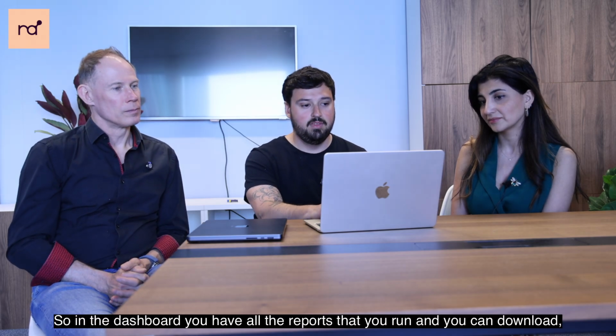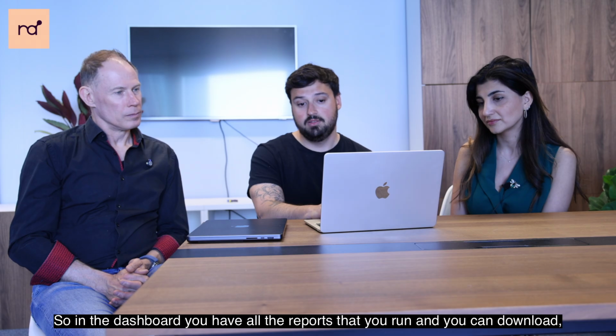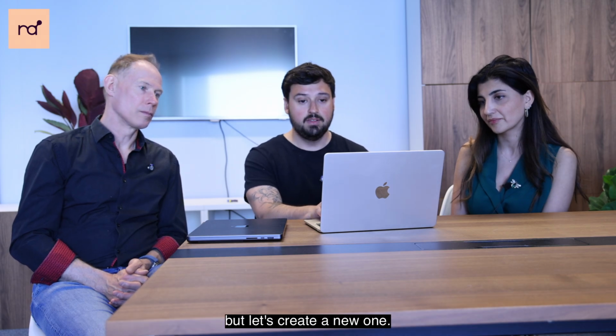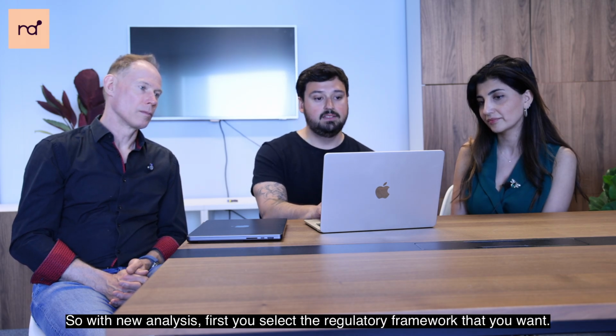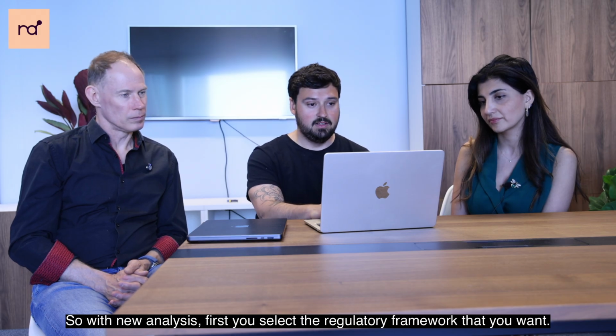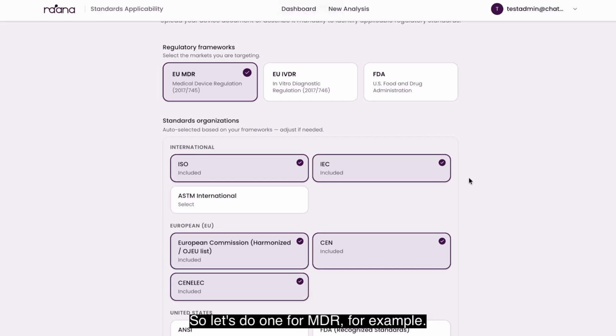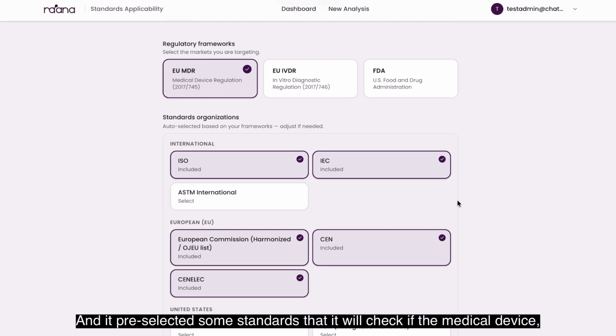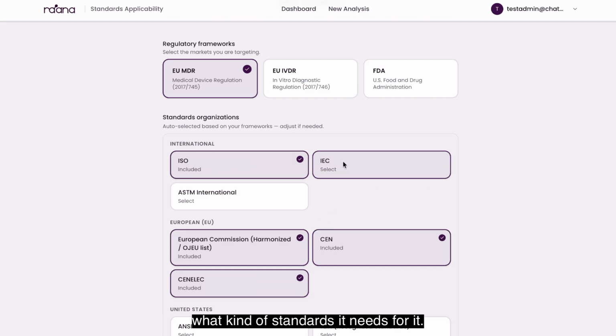Yeah, that's it. So in the dashboard you have all the reports that you run and you can download, but let's create a new one. So with new analysis, first you select the regulatory framework that you want. So let's do one for MDR, for example, and it pre-selected some standards that it will check for the medical device, what kind of standards it needs.